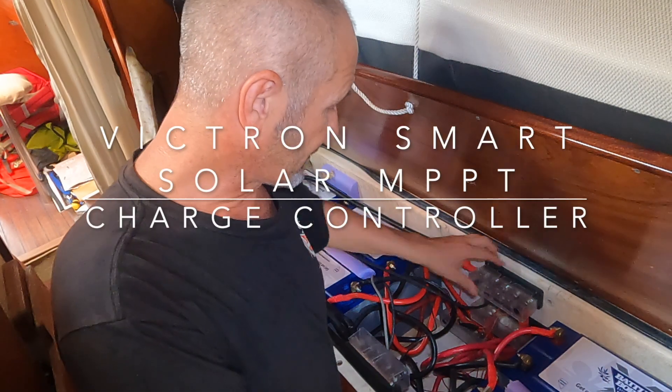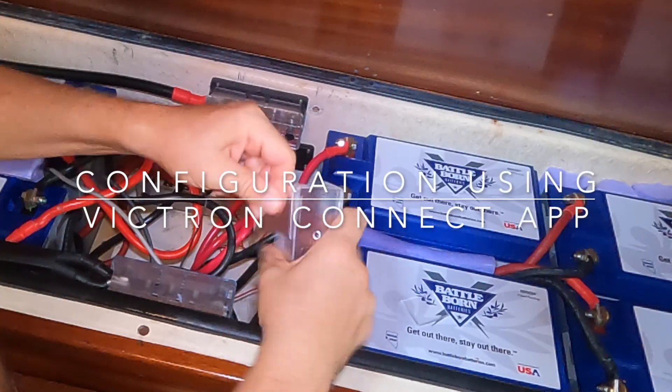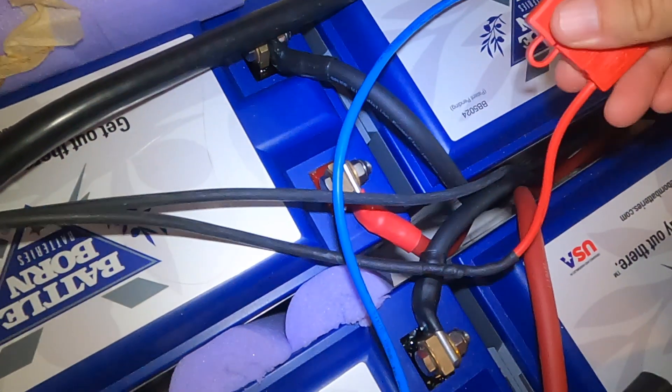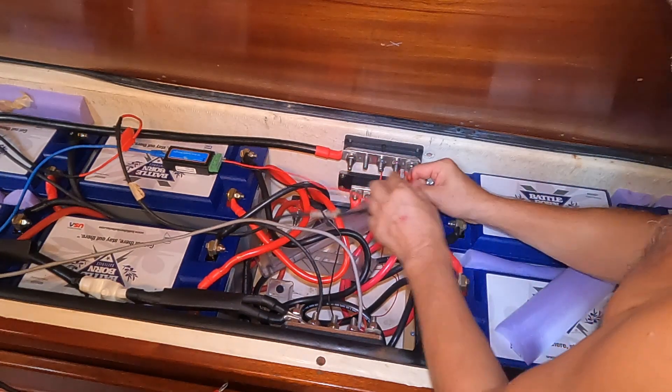So I've just been putting the finishing touches to the battery bank. I've put the protector plates over the bus bars and fuses, tidying up some cables. On the solar side I've taken the 40 amp inline fuse off and replaced it with a 50 amp circuit breaker.